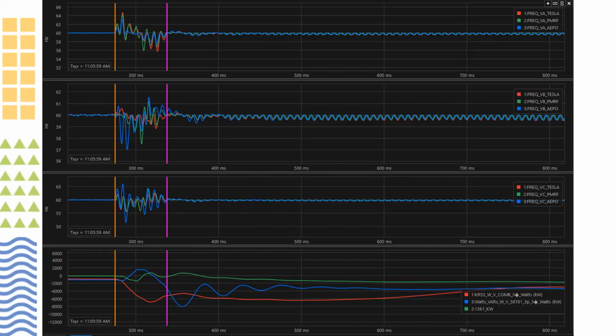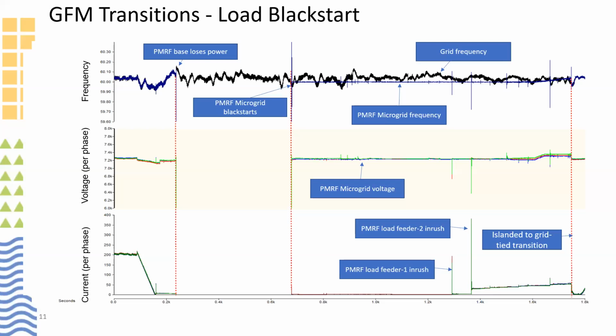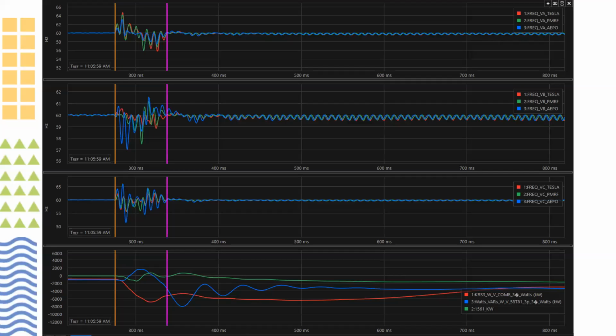This got me pondering. This is like fresh off the press. So it got me wondering, going back to that, the one plot that I had 2 different frequencies, I've been kind of pondering that, what's going on. So we were able to actually trigger a high-speed DFR data that samples at 7,680 samples a second, GPS time-stamped, and I was able to get all 3 major PV battery storage systems, high-speed records for all of them. And I was like, oh man, this is the honeypot. I'm going to see what's going on. But unfortunately, the DFRs they won't plot frequency at high speed.